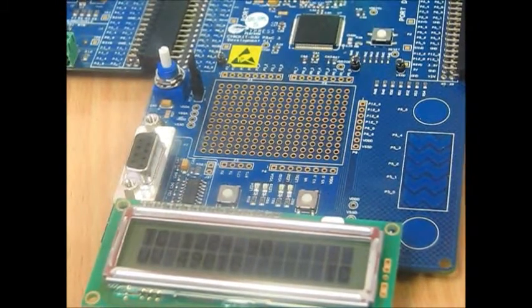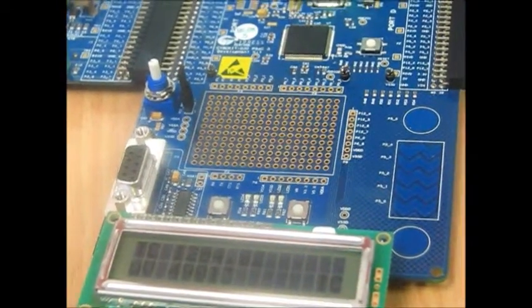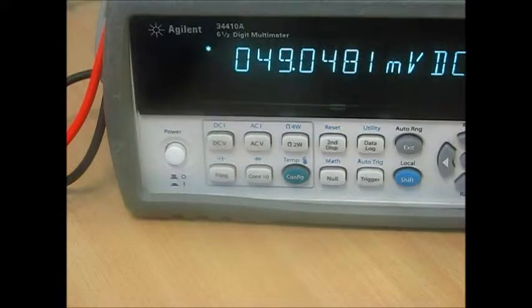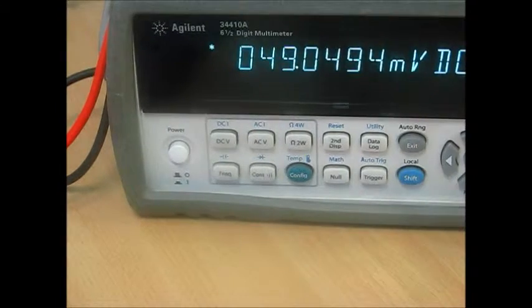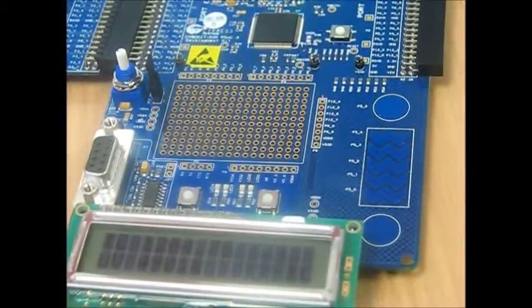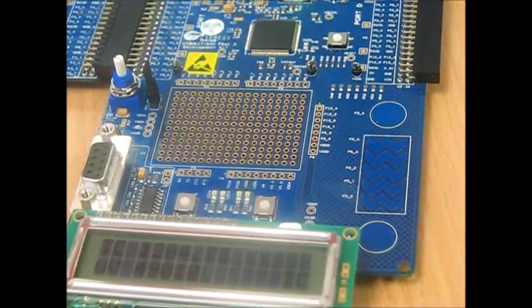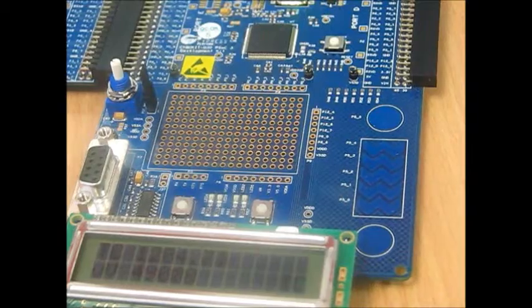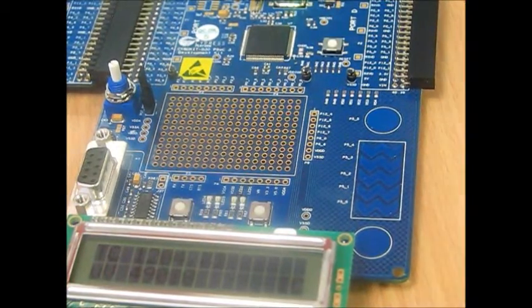Let's check what is the value on the standard multimeter. The standard multimeter reads 49.0494 millivolts. That's a difference of approximately 30 microvolts. Now let's see what calibration can do to it.